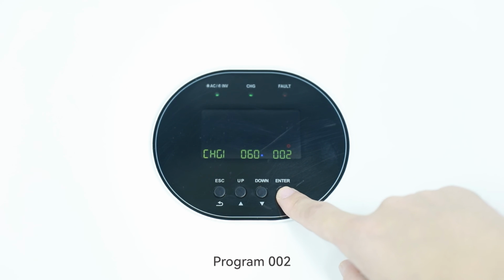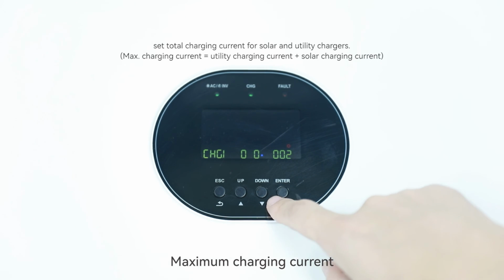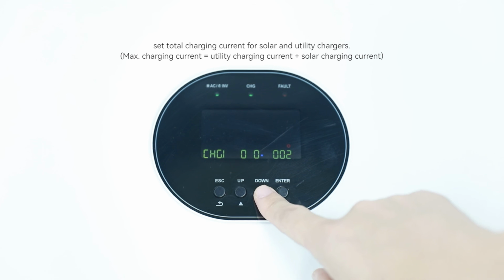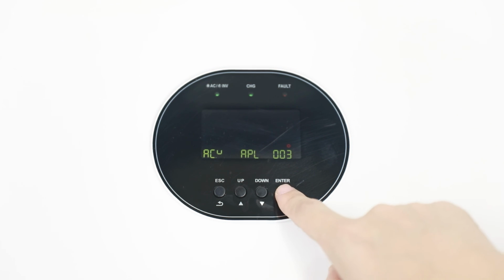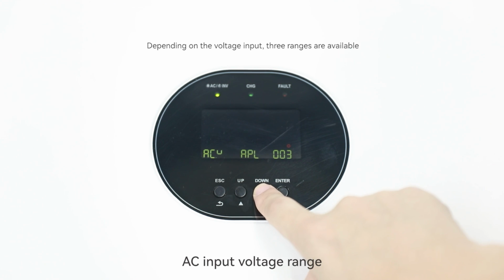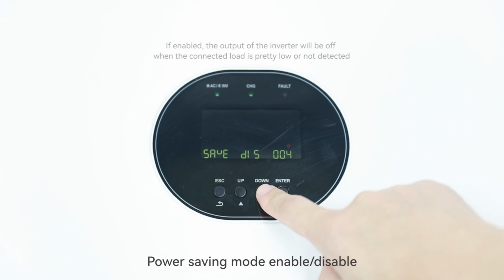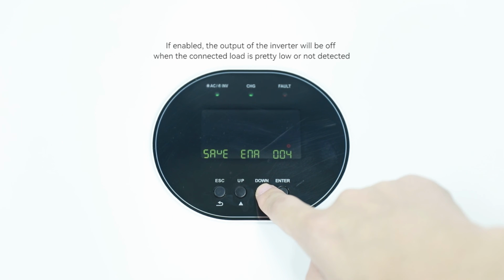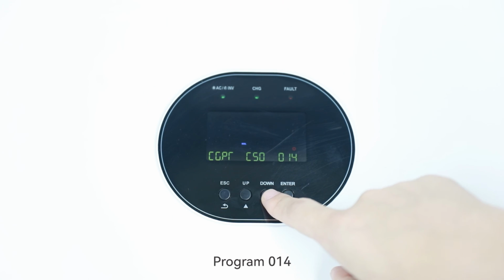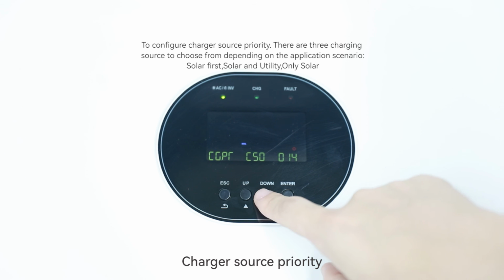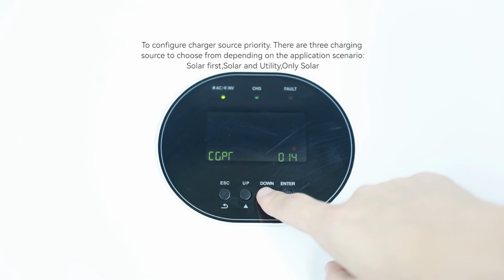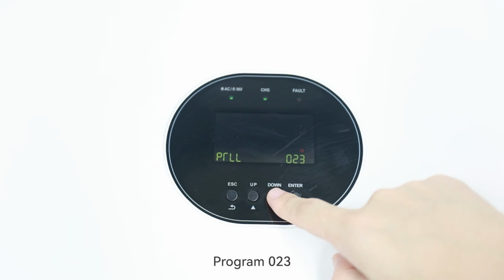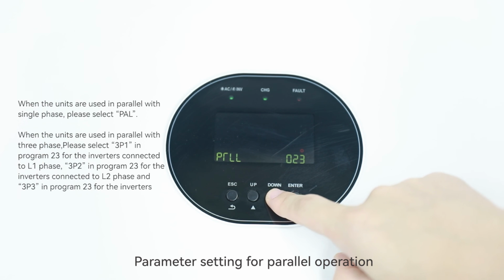Program 002, maximum charging current. Program 003, AC input voltage range. Program 004, power saving mode enable or disable. Program 014, charger source priority. Program 023, parameter setting for parallel operation.